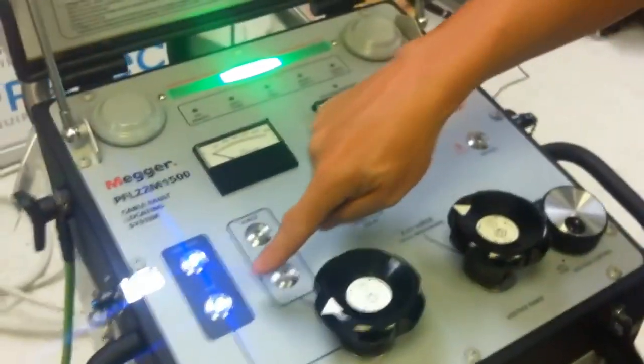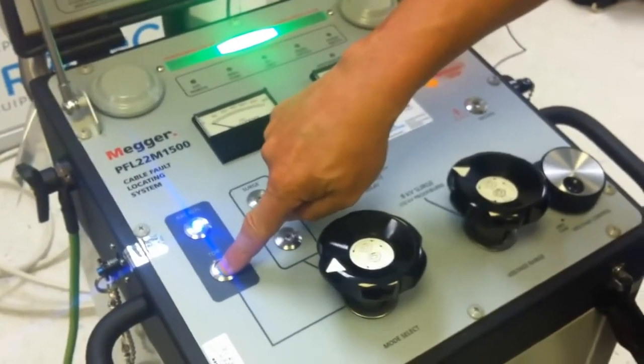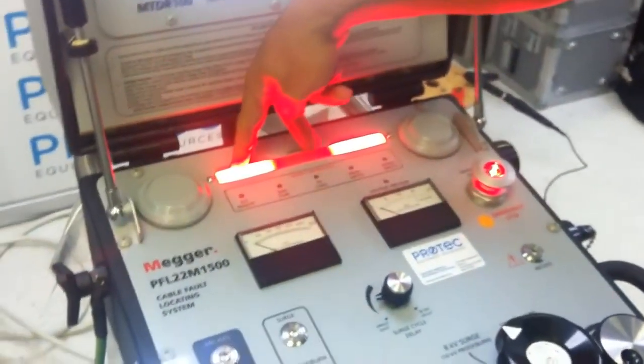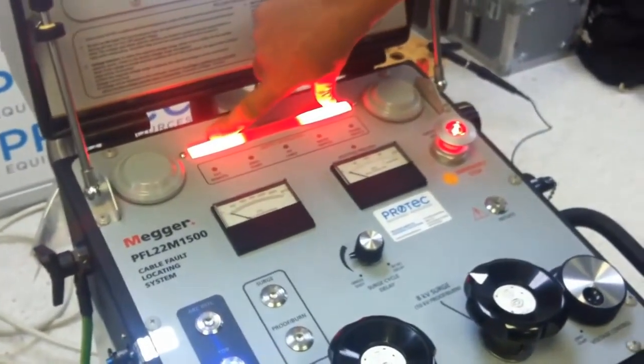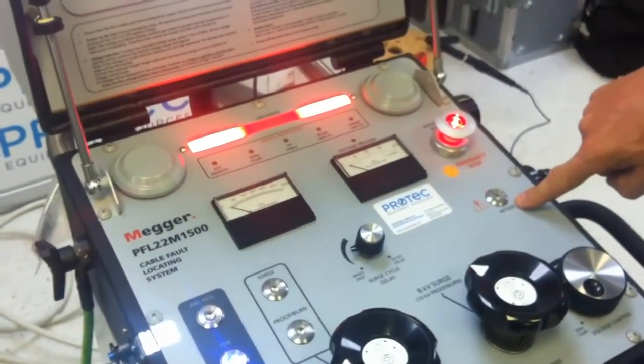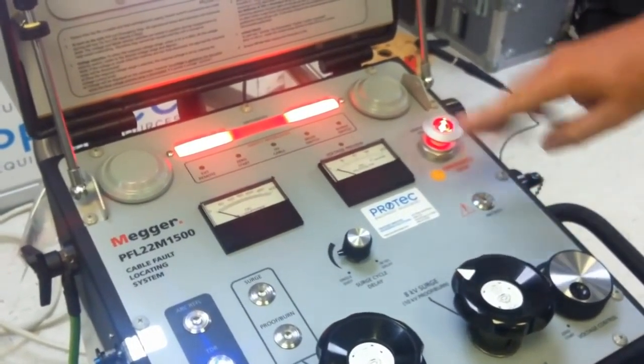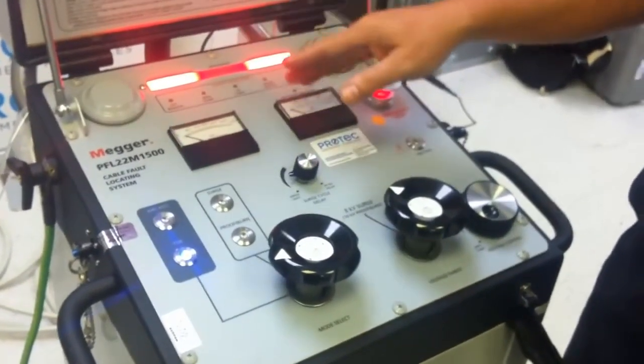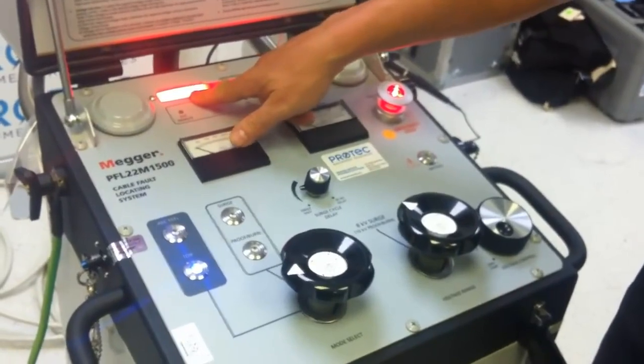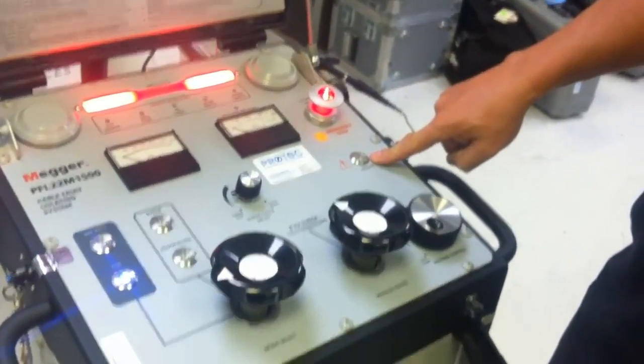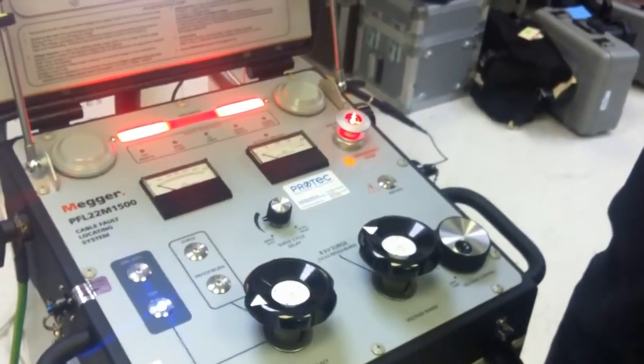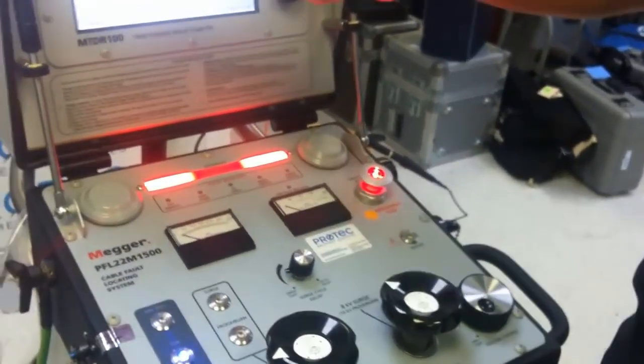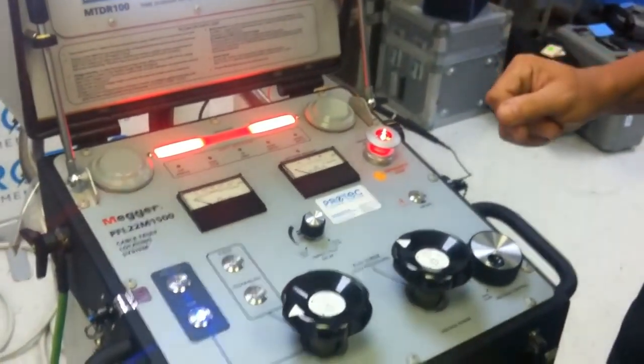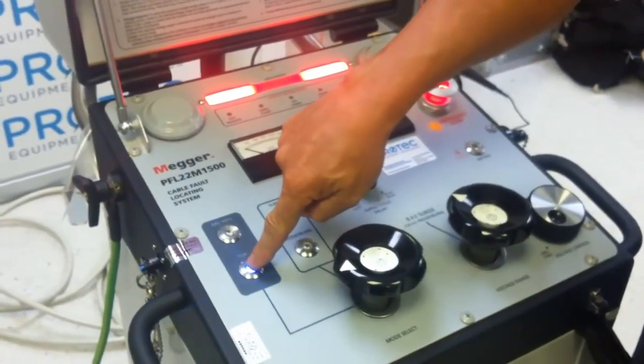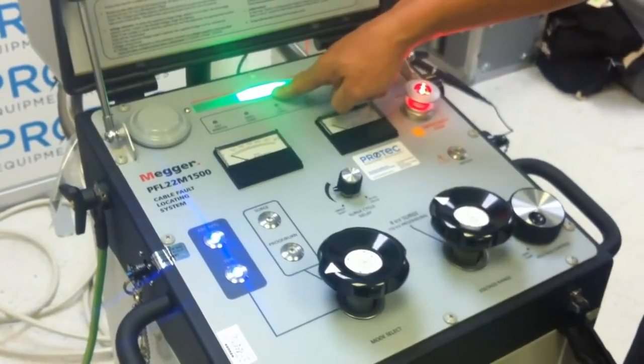Now, as I mentioned before, if I select TDR as my technique, the system will go out of ground and it will apply the red bars, but notice that the initiate lamp will not illuminate. So what the instrument is reporting back to me is that I am no longer in an earth grounded state on my high voltage system. I am in an elevated test mode. However, I cannot apply any high voltage. So if the operator is now handling the test leads and is making a change from phase A to phase B to phase C and so on, they can do so safely. To exit the mode, again, you just push the button a second time. We're back to the grounded state.